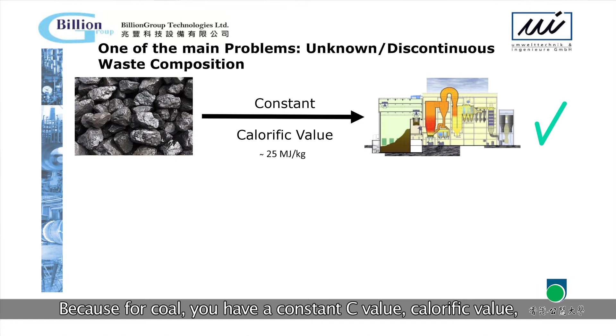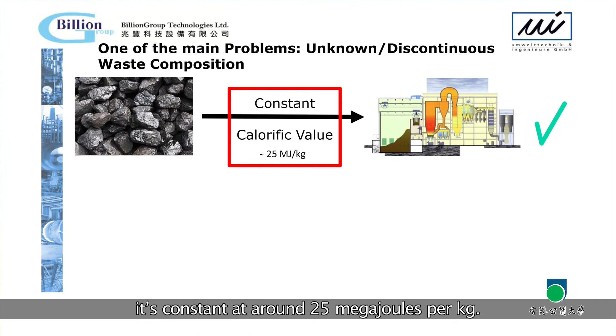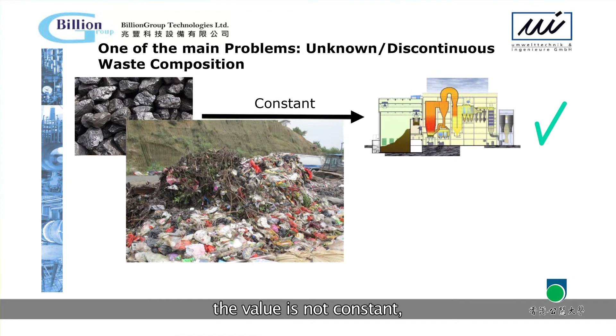Running a waste-to-energy plant is quite difficult, unlike running a coal plant, because coal has a constant calorific value, around 25 megajoules per kg. But for a waste incineration plant, the value is not constant; at different times in the year, like Chinese New Year, Easter holiday, summer or winter, the composition of the waste differs, so the internal calorific value of the waste differs. Building a waste incineration plant to cater for different calorific values is extremely difficult, and the efficiency will be very low.